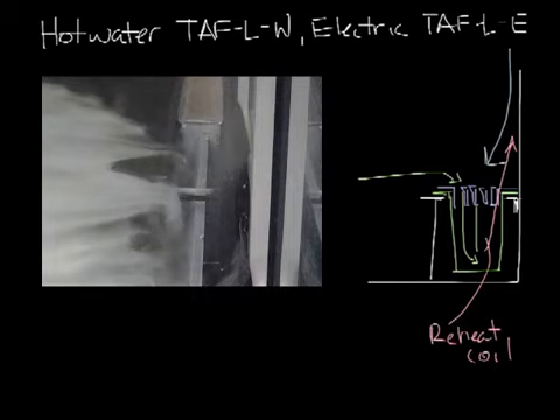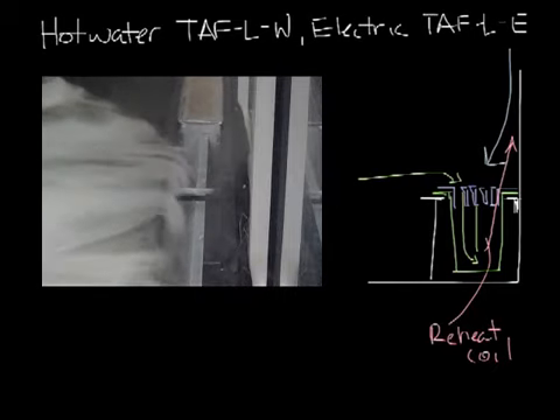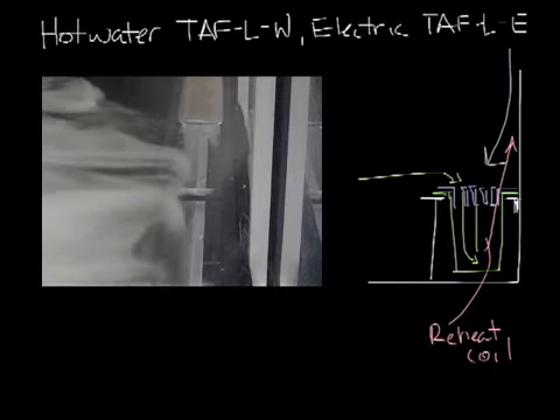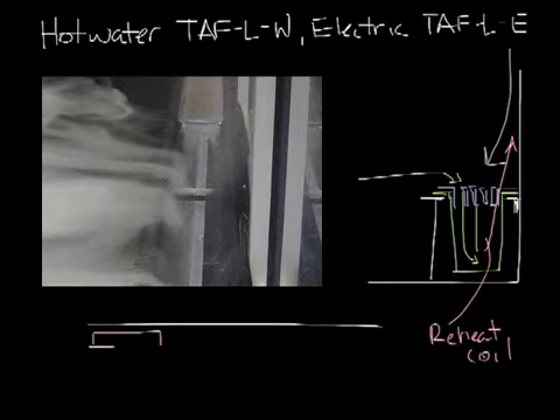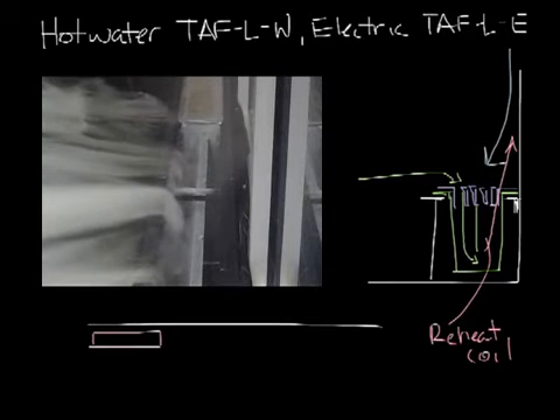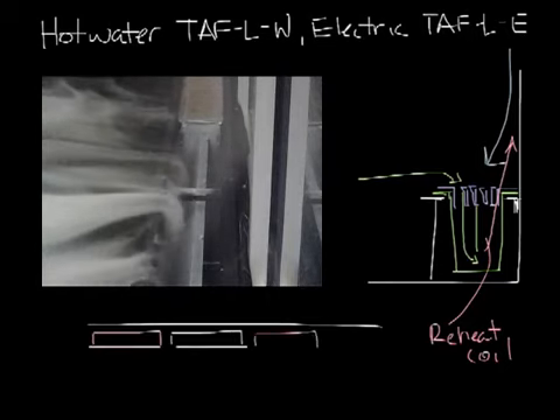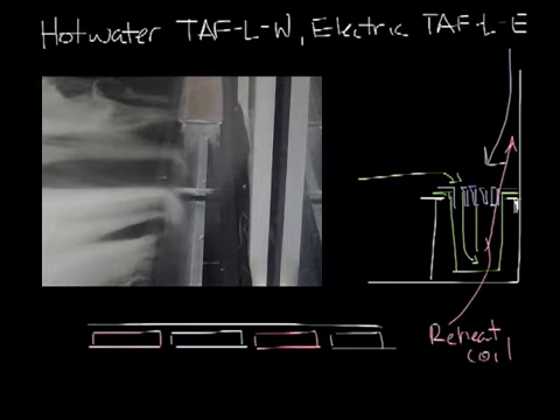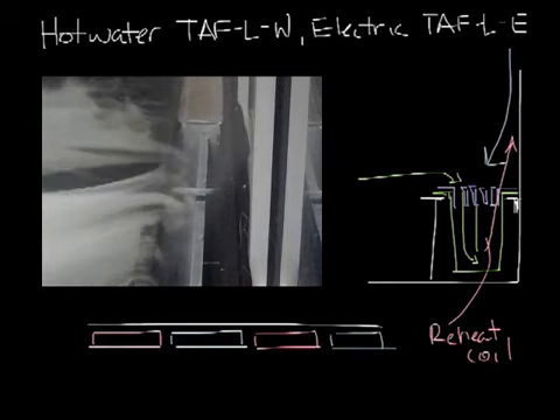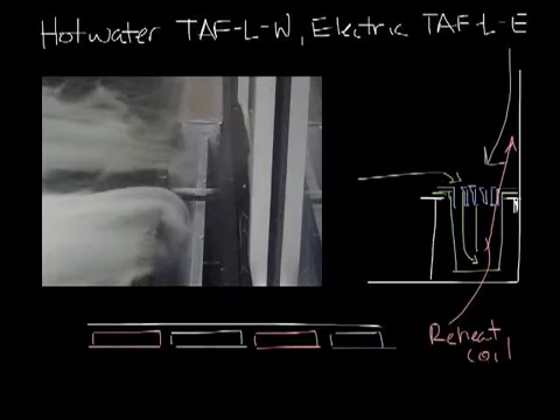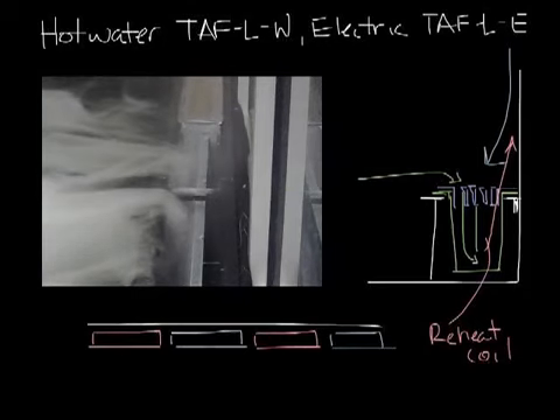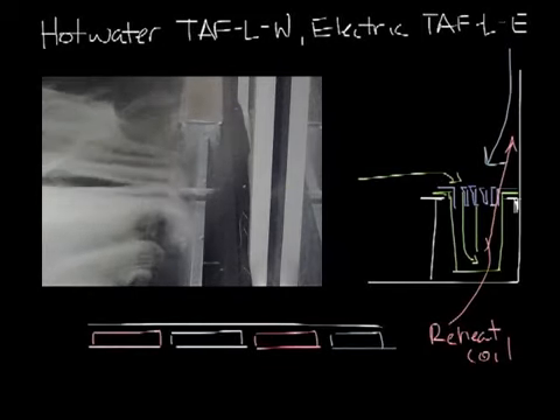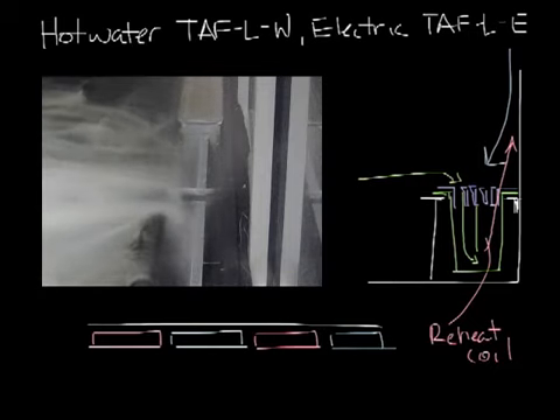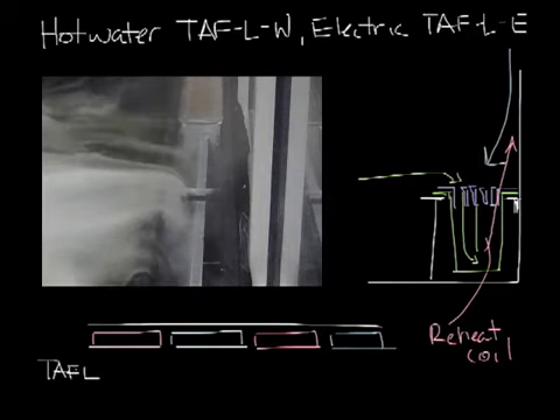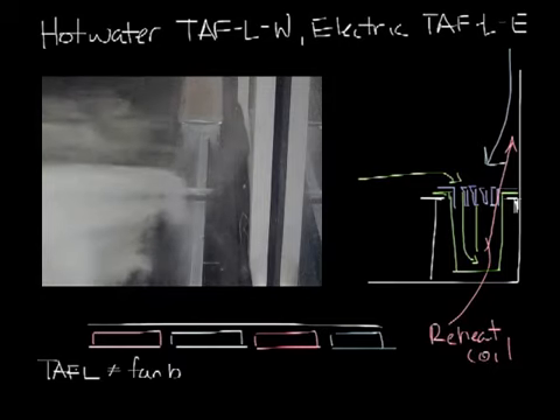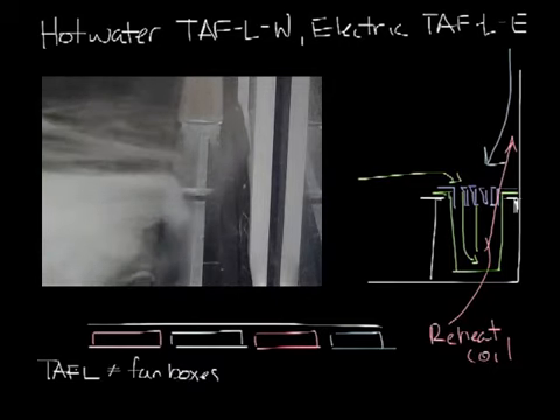So how you would use this is that you would alternate cooling and heating units across the perimeter. So it'd look kind of like this, with maybe a heating unit, a cooling unit, a heating unit, and a cooling unit. Or maybe it's just 2 heating units and 1 cooling unit, depending on your load. But the CT would be continuous across the top, so it would look from the room to be one continuous grill. The TAF-L system has addressed the perimeter heating challenge in a way that doesn't add fan boxes and doesn't break the stratification layer.